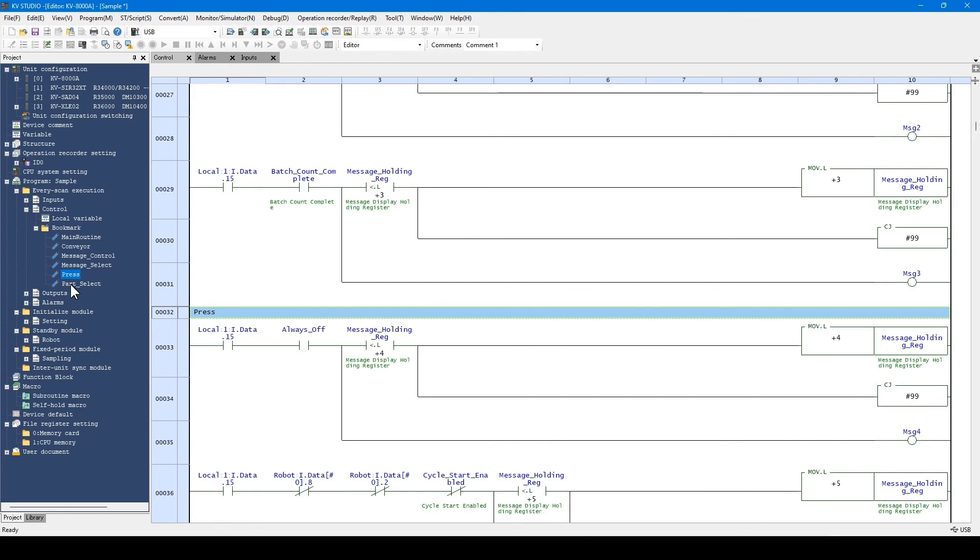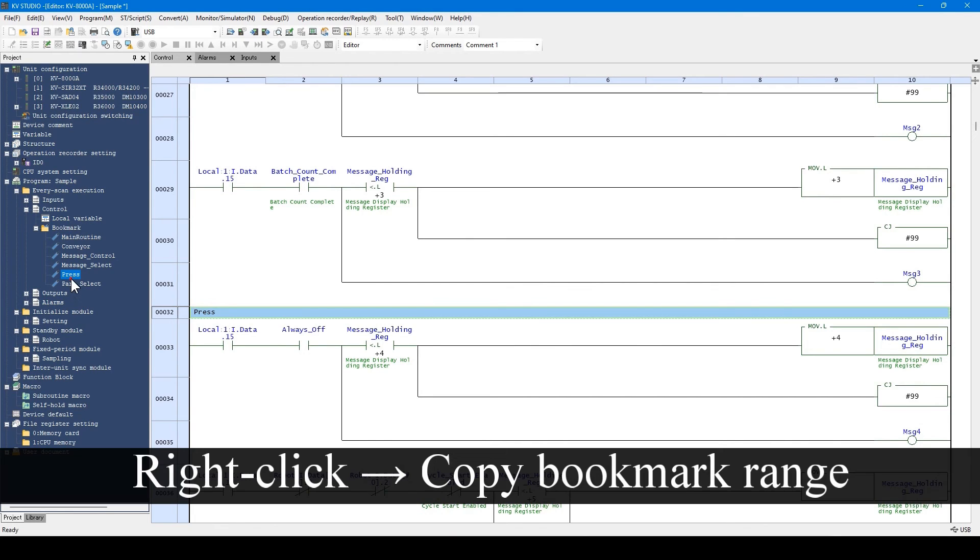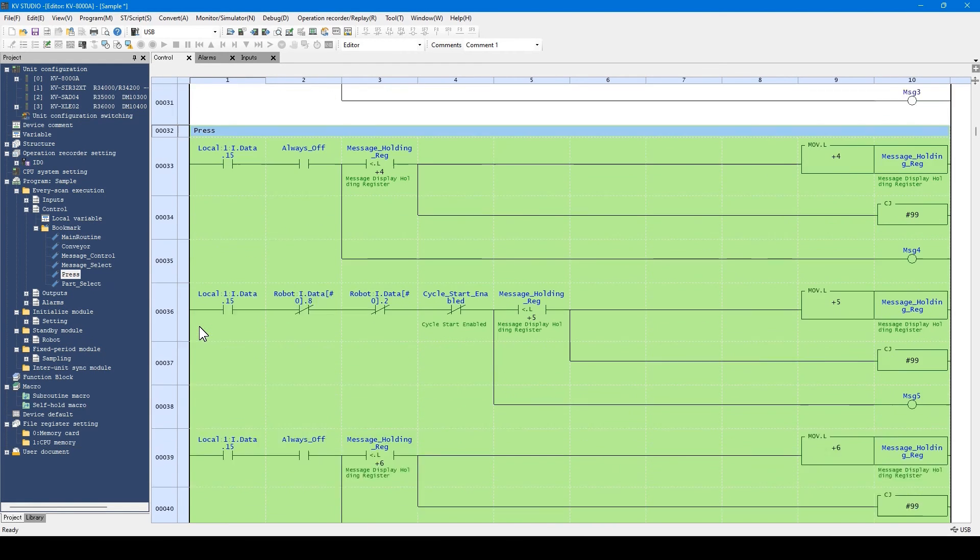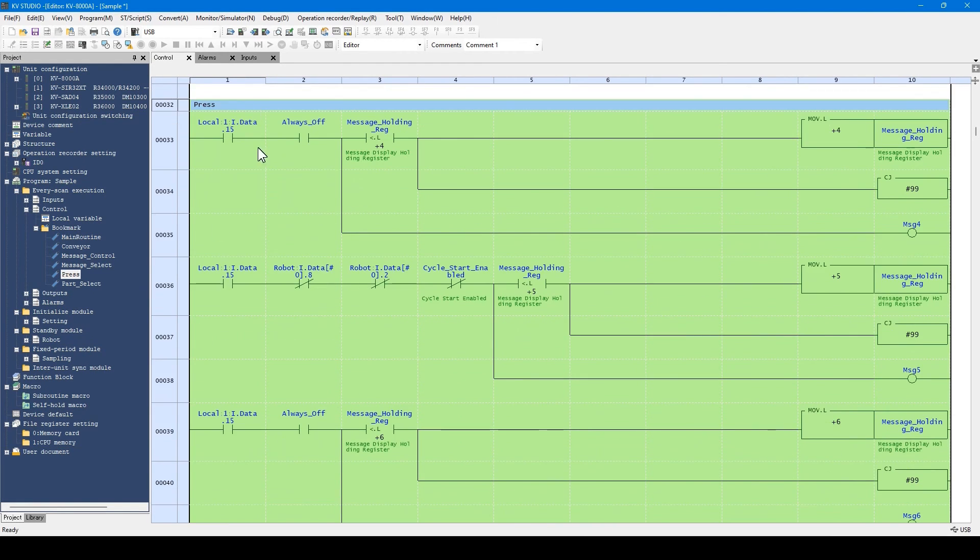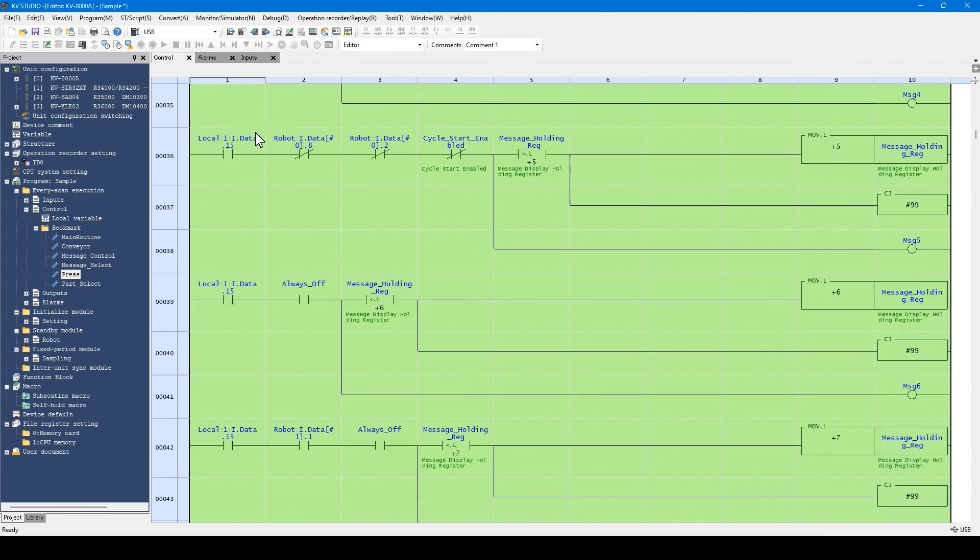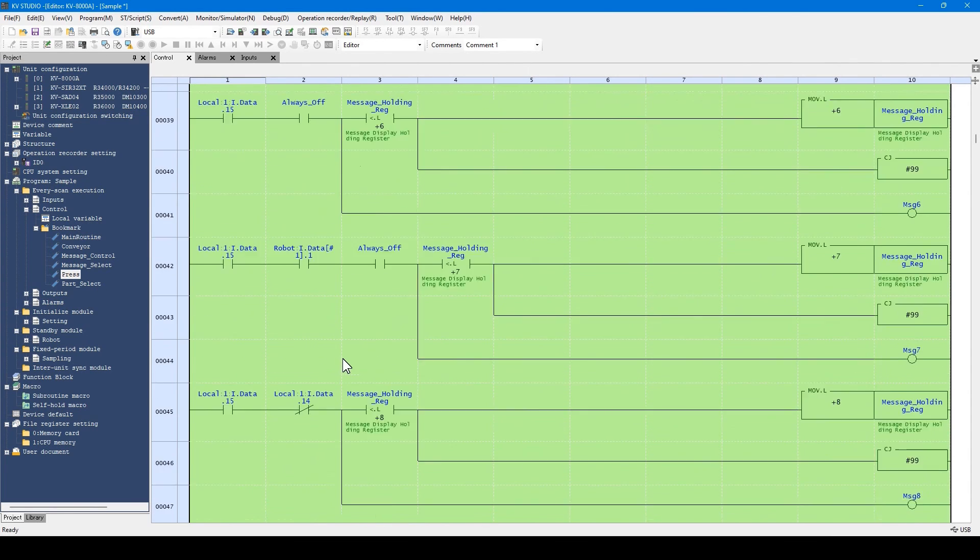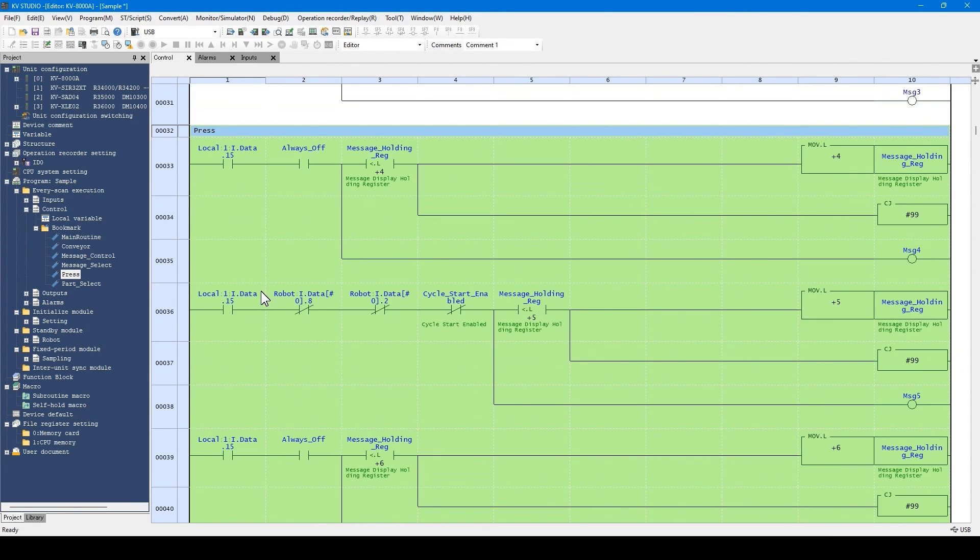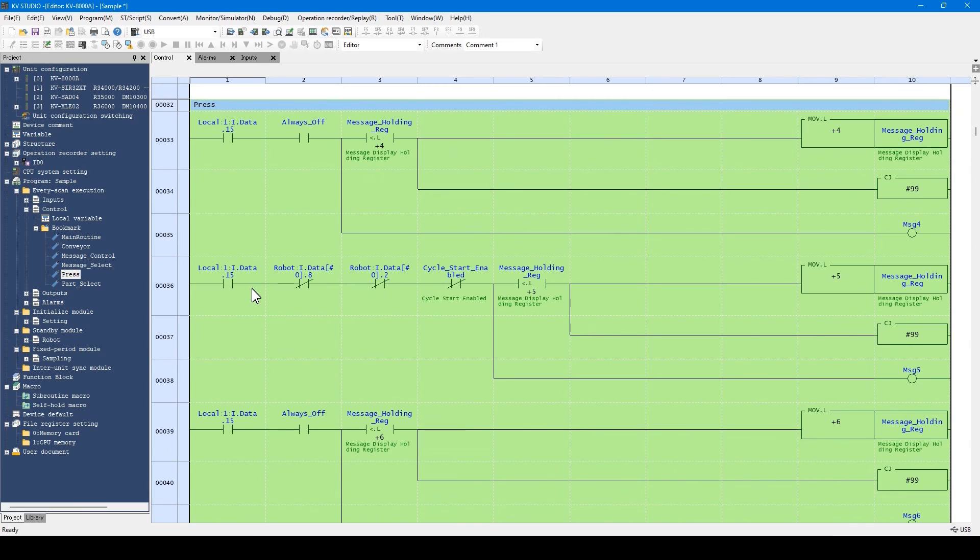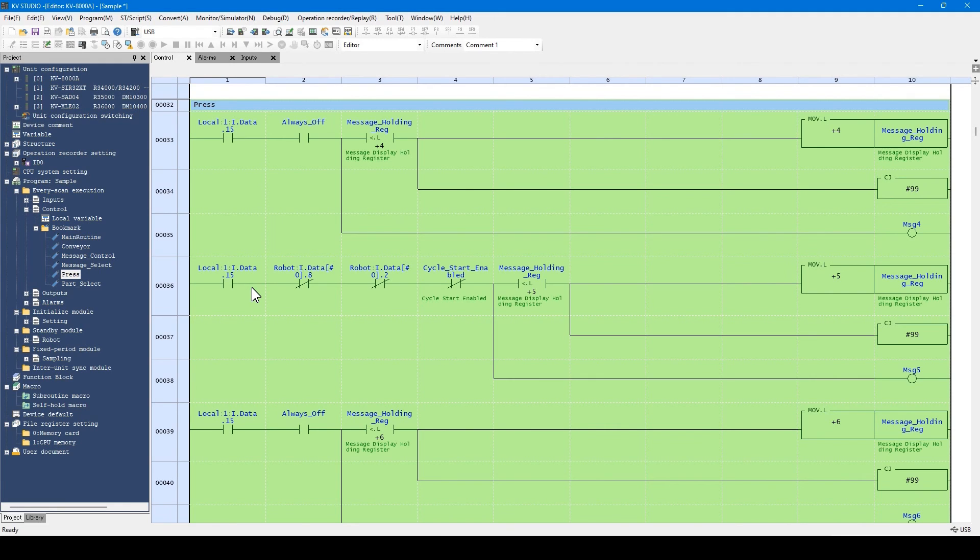In addition, bookmarks can be copied from the right-click menu. When copied, the bookmark itself and the ladder program in the bookmark are selected and copied. You can paste the copied bookmark to a different module or a different program. Therefore, by separating modules through using bookmarks, you can reuse the ladder program within a bookmark. Thus, copying programs becomes easier.